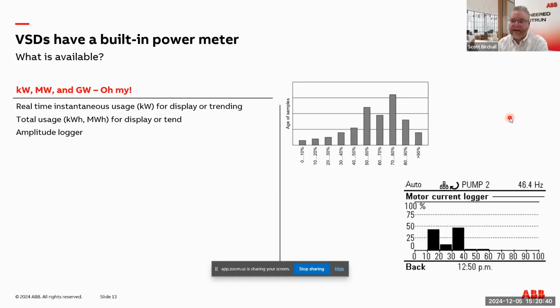So you as a facilities manager, energy analyst, depending on what your situation and your role is, you can really configure this up to however you want it. But the key is integrating it with your building automation system so you can read that information over BACnet or Modbus. There's amplitude loggers in there, so I can even see if I didn't have something integrated. I can even take a look and see, hey, how often is this drive running at 60 to 70% load versus 70 to 80% load? This is a screenshot of one that I took on Monday of our geothermal condenser water pump. So I can see that this particular pump is quite oversized, and typically it is at less than 50% current capacity. So perfect example of equipment being oversized.